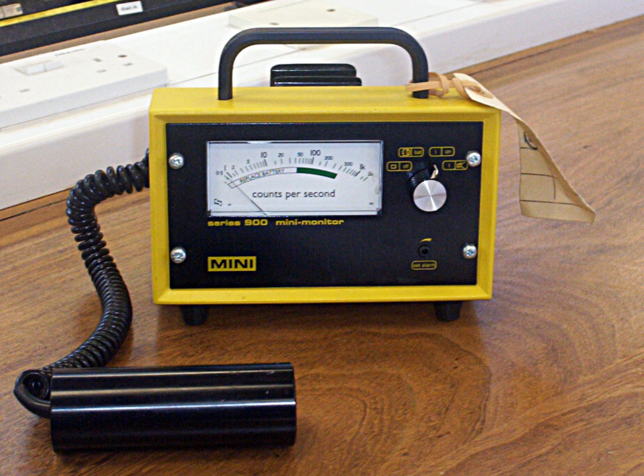The term Geiger counter is commonly used to mean a handheld survey type meter; however, the Geiger principle is in wide use in installed area gamma alarms for personnel protection, and in process measurement and interlock applications. A Geiger tube is still the sensing device, but the processing electronics will have a higher degree of sophistication and reliability than that used in a handheld survey meter.